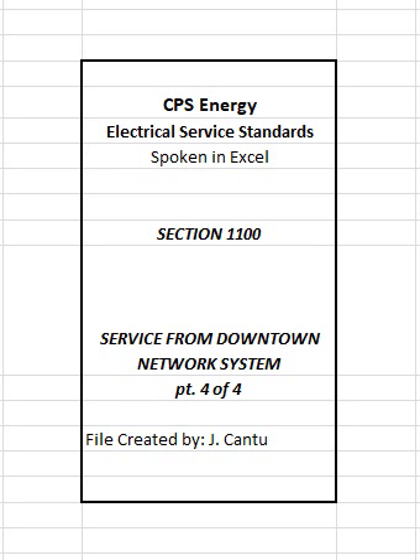A. Multiple meters. Where multiple meters are to be supplied by a 208Y/120 volt service and individual tenants do not require three-phase service, then 120/208 volt 3-wire meters may be permitted by CPS Energy provided that metered loads can be balanced on the three-phase system. Each case must be approved by CPS Energy, refer to Figure 1805. B. Modular metering. In some instances involving residential type loads, modular metering that meets CPS Energy specifications may also be permitted. Each case must be approved by CPS Energy. Modular metering is not allowed to supply commercial type loads, refer to Figure 1814.